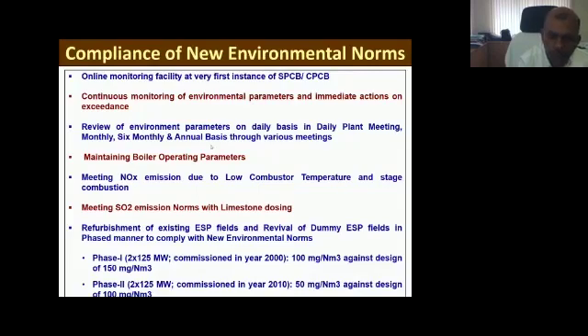For SOx norms, we are feeding limestone. We have our own captive mines for limestone, but the quality is not good, because yesterday and today also I have seen a lot of discussion that for an FGD plant there is a major requirement for limestone quality. Our limestone is of very poor quality, with a CaO content of around 41%, 42%. Even sometimes we go below 40%, in the range of 37%, 35%. This creates another problem, because once its quality goes down, feeding will be more and reactivity will also be less. So this creates a lot of problems.